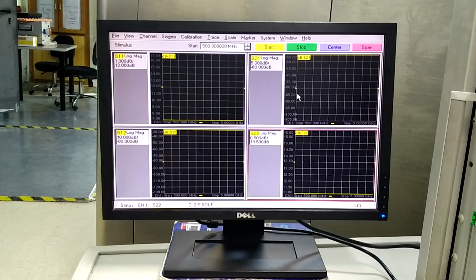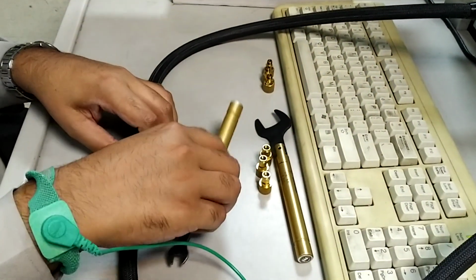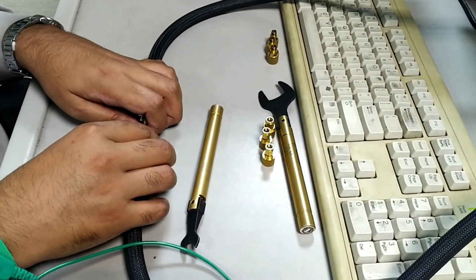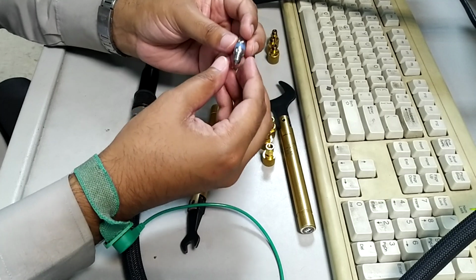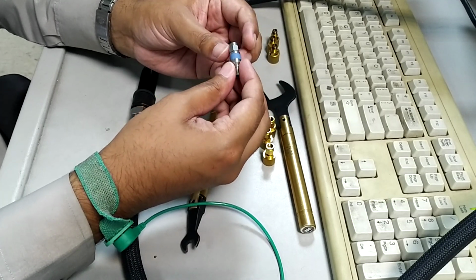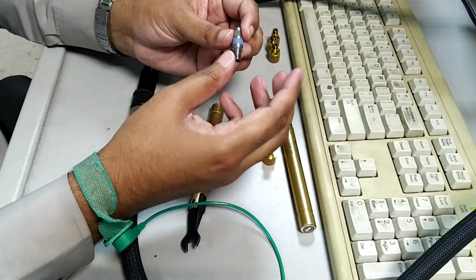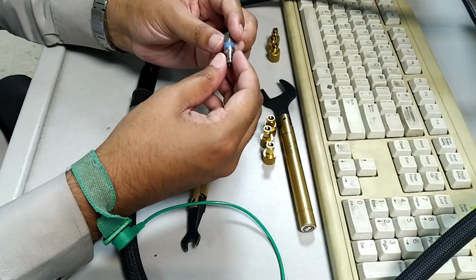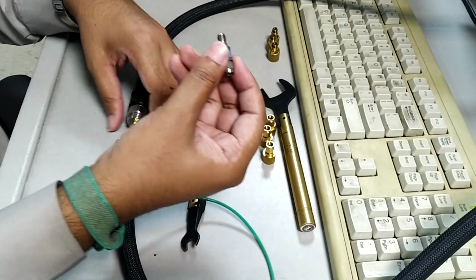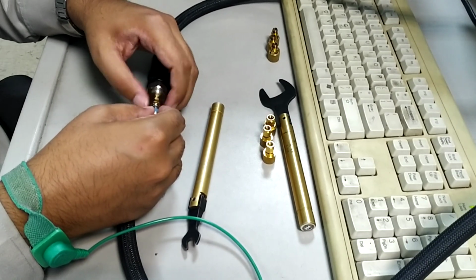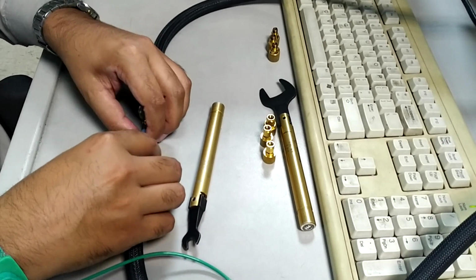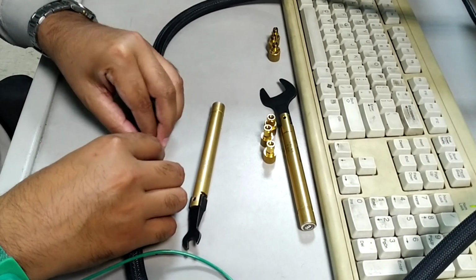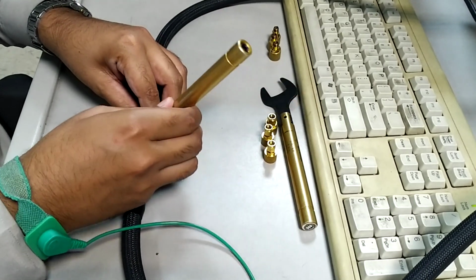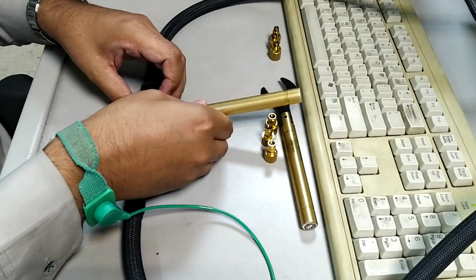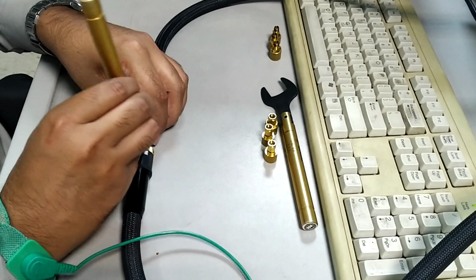So now I will disconnect this through connection and connect an attenuator in between them, just to validate that my calibration is fine. This is an attenuator standard. This is a minus 10 dB attenuator, which means if I connect this one and display the transmission parameter S21, S12, it should show me minus 10 dB or near to minus 10 dB, plus or minus 0.5 dB fluctuations in its value. So let's connect this one. I connect the female to port number 1 and the male to port number 2. We call this a verification device that validates your calibration.